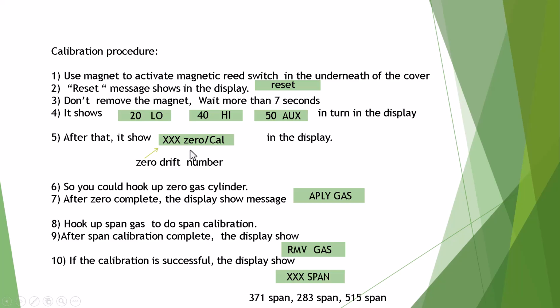You do the calibration, zero calibration. After zero calibration, the display shows apply gas. So hook up the span gas to do span calibration. After span calibration is complete, the display shows RMV gas, remove gas. That means the calibration is complete. If your calibration is successful, the display just shows this: XXX span, where X means the number, for example 731 span, 283 span, 515 span. That means the calibration is successful. Okay, that is a very simple calibration.